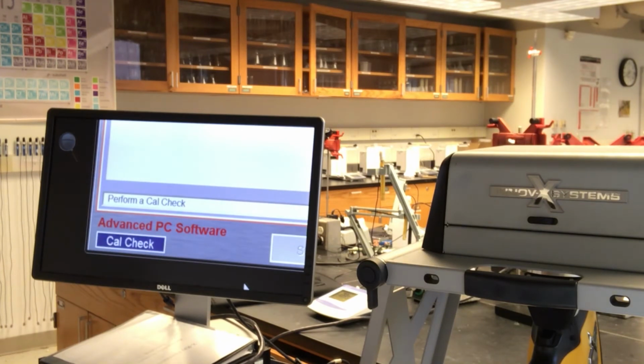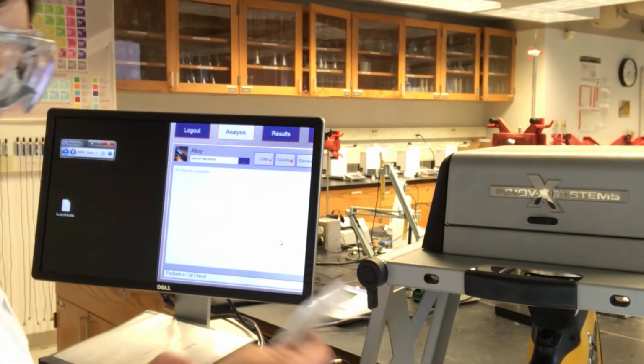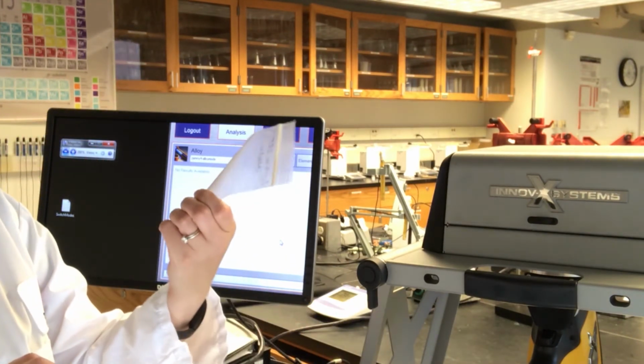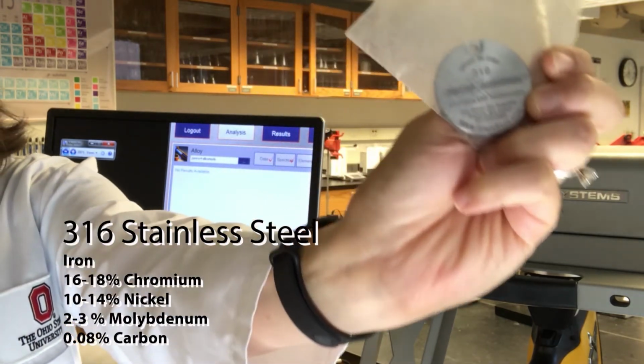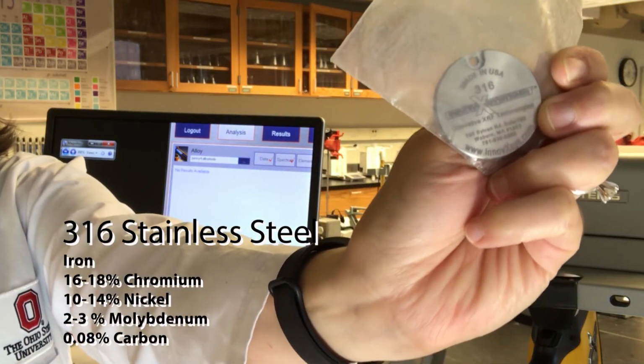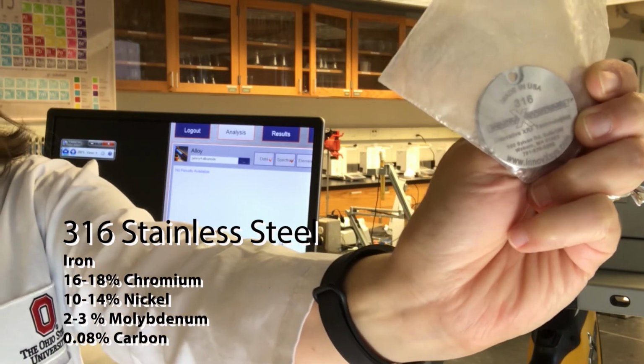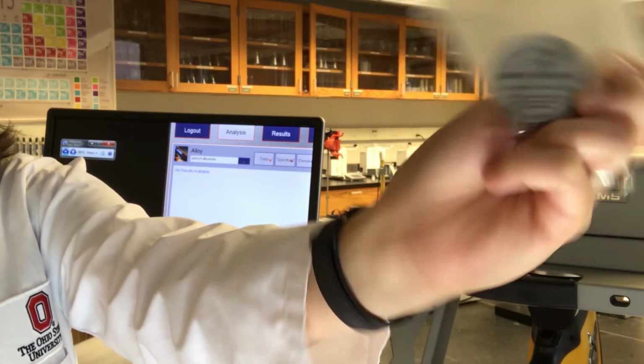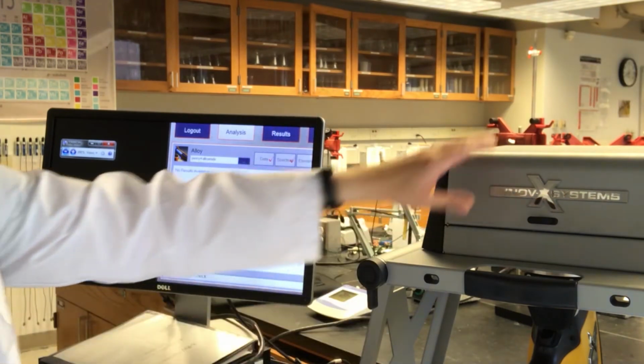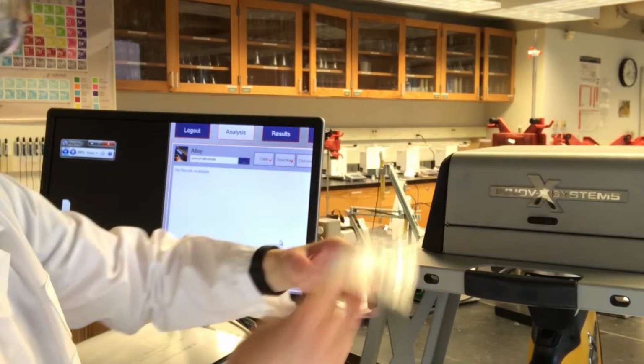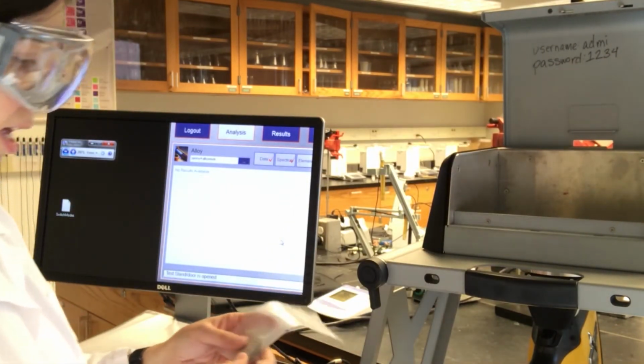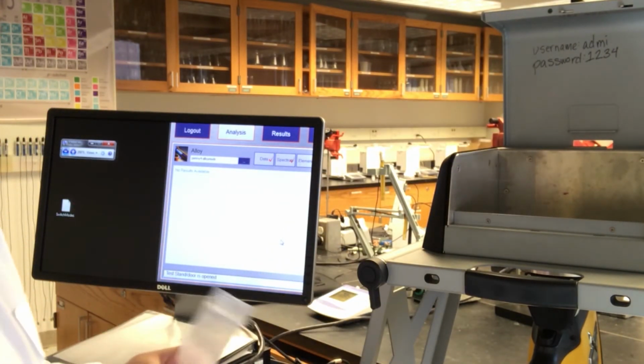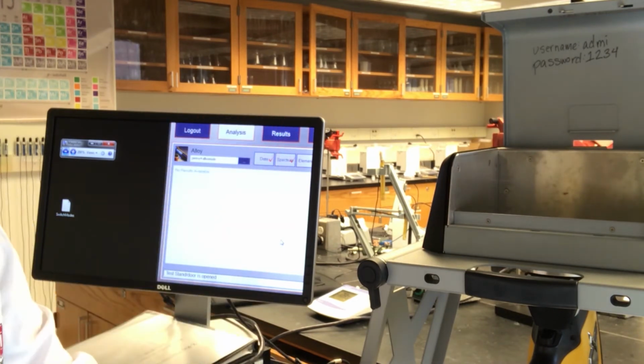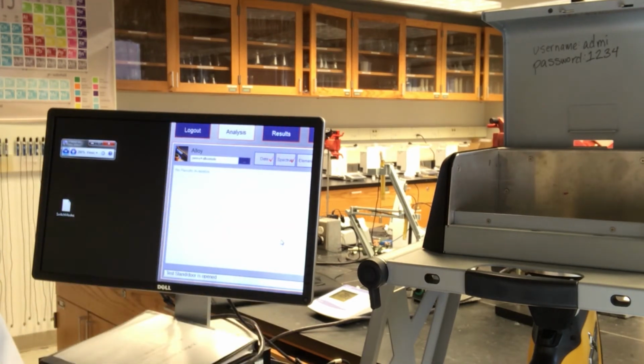So the first thing we have to do is perform a calibration check. And the instrument comes with a calibration disc. It's a certain type of steel, the contents of which are well known, and that's built into the software. We leave this disc in the plastic, and usually it's found inside the instrument itself. So we keep it there for safekeeping so that it doesn't get lost. And all we're going to do is put this disc on the X-ray source and detector. So let me show you what that looks like.